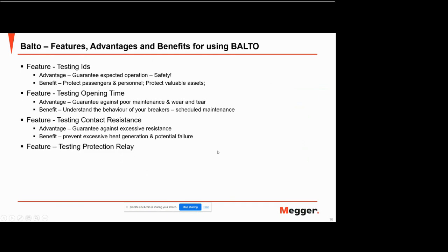And finally, the other benefit for Balto is the ability to test your protection relay. Here we can ensure that we can actually set the correct parameters on your relay to make sure that it's working to specification. But also, the important thing here is that when we test the relay, we're testing the entire system as well. We're testing the relay, we're testing any current sensors, we're testing all of the connections, and we're testing the DC high-speed circuit breaker. So it's testing the entire protection scheme with the Megger Balto.